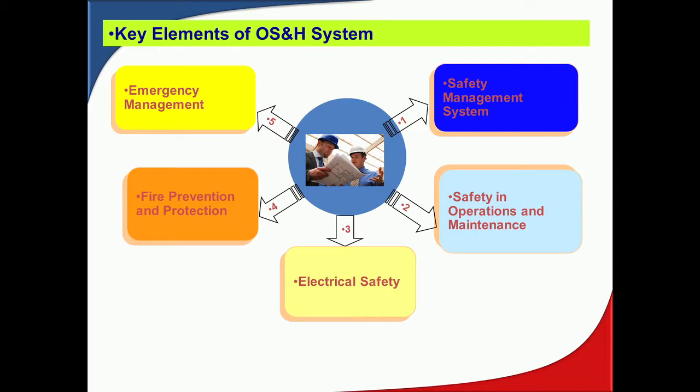Then electrical safety: are the electrical hazards identified, are proper electrical safety measures taken, are proper licenses availed? In terms of fire protection, do they have a proper hydrant system and fire protection system, is it maintained properly, is it adequate? And in case a fire happens, are they prepared to attack it? Do they have a response team? Do they have mutual aid? Are they trained to handle emergencies?